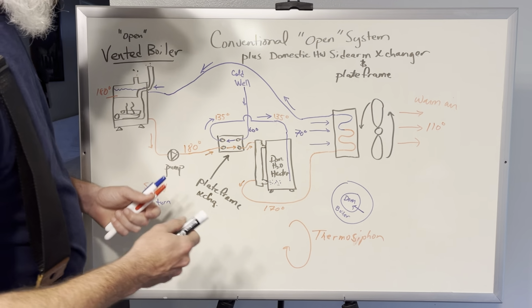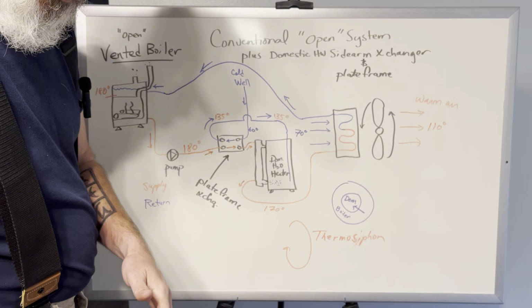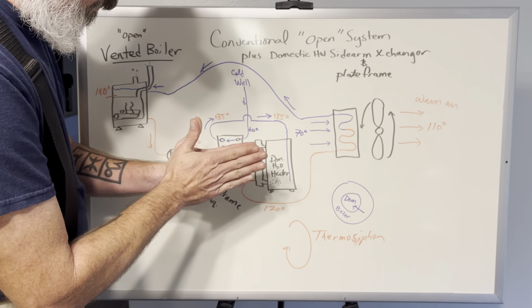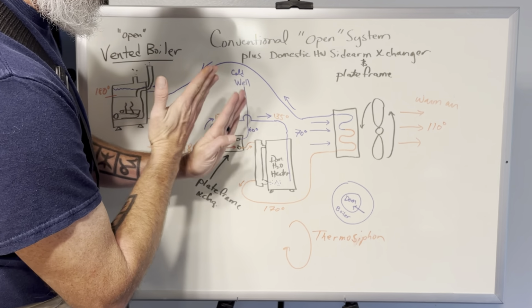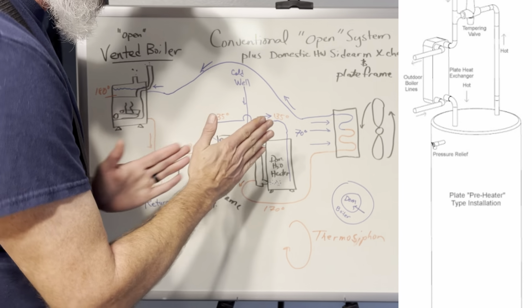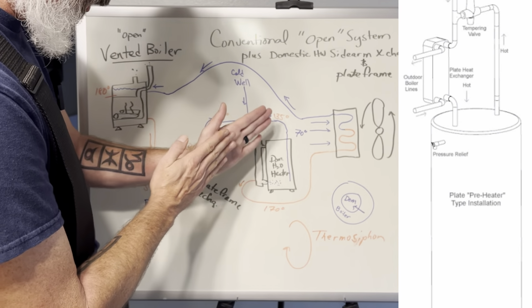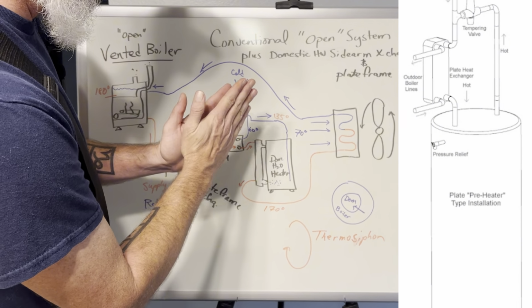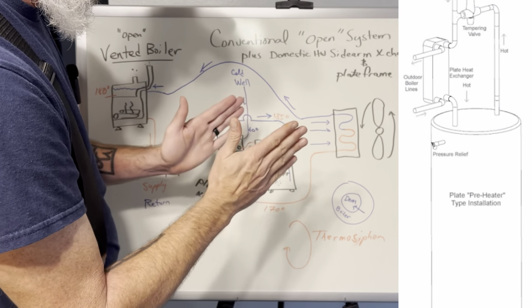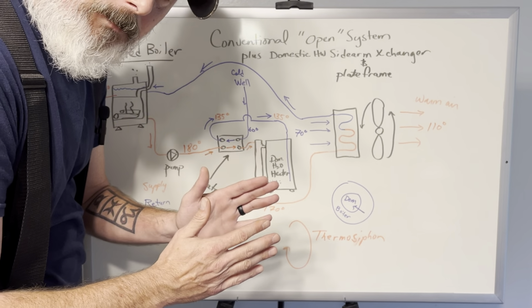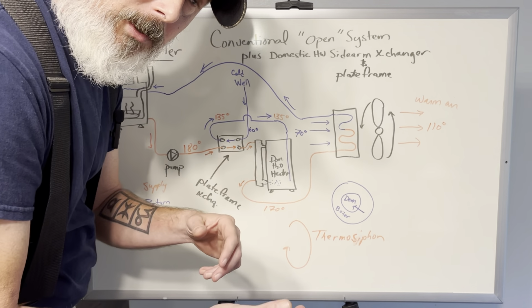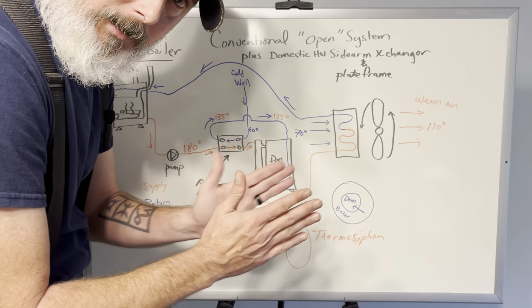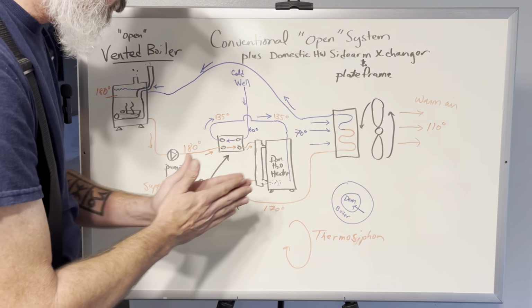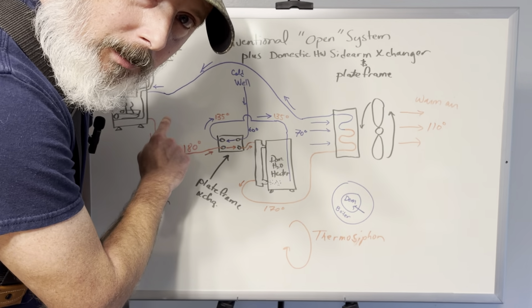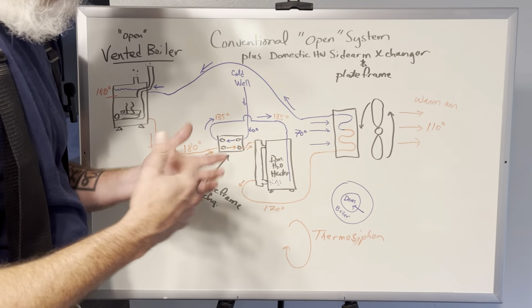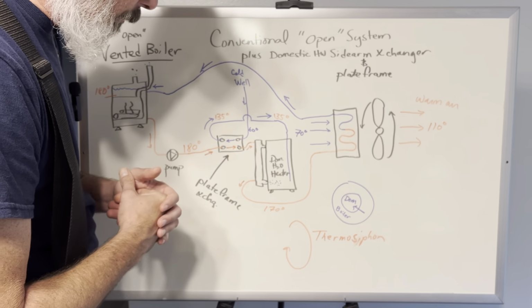And this is basically just a bunch of stacked plates that allow water to pass. Boiler water passes on this channel, domestic cold water passes on this channel, and they're just stacked. And so they give up heat. The boiler gives up heat to the domestic water, but the two water systems are isolated. They're separated, which is good because we should have chemistry in here. If you don't do chemistry, it's just asking for trouble.